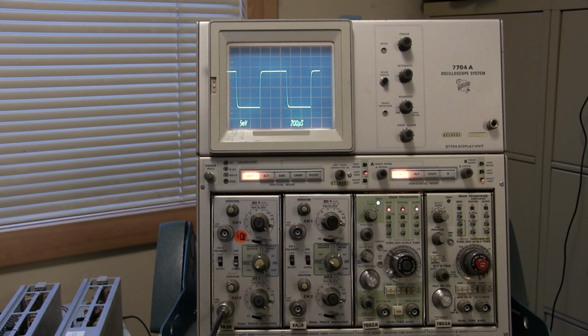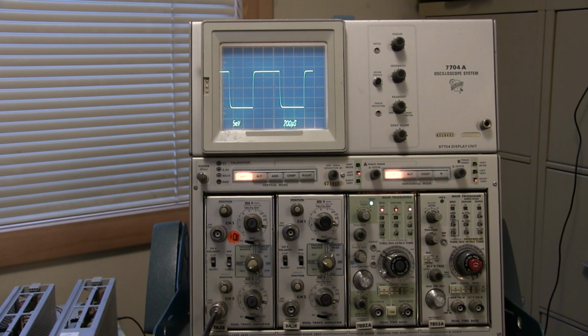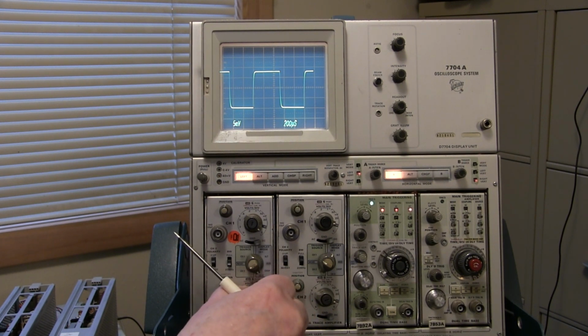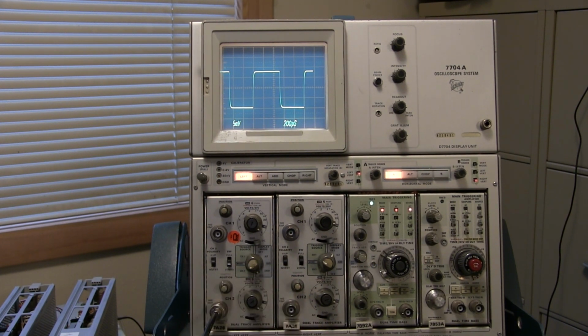The problem with this 7A26 is that I have low gain on channel 2. I set the input to 5 millivolts, and I have a 20 millivolt input, and I should be able to use this by pushing in the variable until it engages with the gain setting control. I should be able to adjust it to four divisions exactly, but about 3.8 won't go.